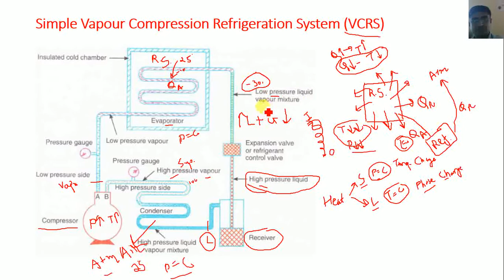After the expansion, the refrigerant becomes a mixed phase, liquid plus gaseous, with a very high amount of liquid but a much smaller amount of gaseous particles. So the high pressure liquid gets expanded in this expansion valve, or capillary tube, and at the outlet its phase becomes a low pressure mixture of the liquid as well as the gaseous phase. So here you can see a liquid vapor mixture.